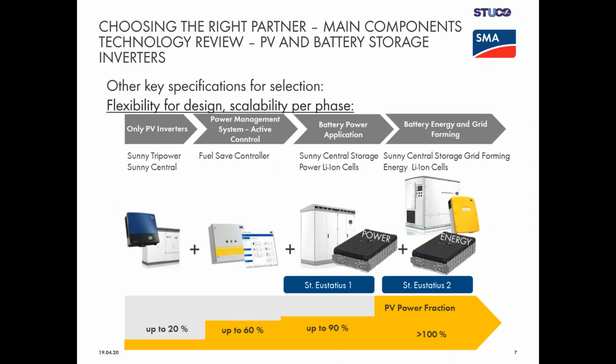This next page shows the main components technology review of when considering to go have a PV application. If we start to the left, basically you can go up to 20% penetration, PV power penetration, without making any considerations.